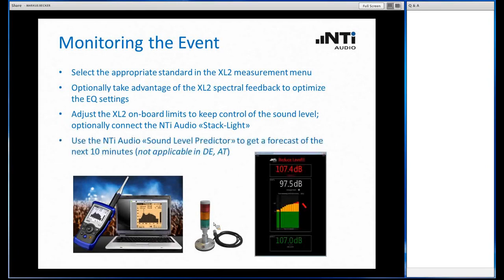And the third option you have is that you use our sound level predictor. This is a nice software which we provide, and this would calculate a forecast of the next 10 minutes. You remember that the LEQ, the key measure, is rather slow in its behavior. So if the sound level rises, the LEQ with a certain delay would reflect that. Because you want to avoid exceeding these absolute limits, the sound level predictor would warn you, pay attention in a few minutes time, if nothing is changed you would exceed that limit. That's the message it gives you, so it allows you to turn down the level of your installation a little bit to comply to the law. Unfortunately, this LEQ predictor does not work for the German and Austrian legislation, this is due to technical reasons. It cannot be implemented on this basis.